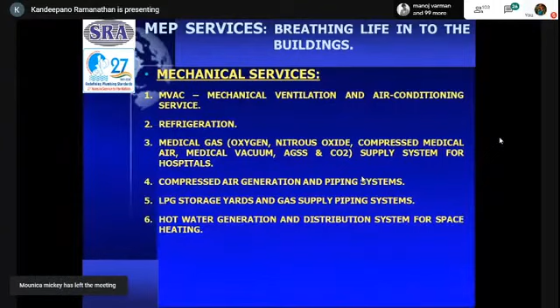Then compressed air generation and piping system, both for hospitals as well as industries. LPG storage yards and gas supply piping systems, mostly for industries. Hot water generation and distribution system for space heating as an air conditioning requirement in cold climates. We generate hot water and distribute it to every room, and using heating coils we produce a warm environment in cold climate areas. Like we do it not in Chennai of course, but in northern India, in Shimla, Kashmir, places where the temperature is very low, or even in Ooty.